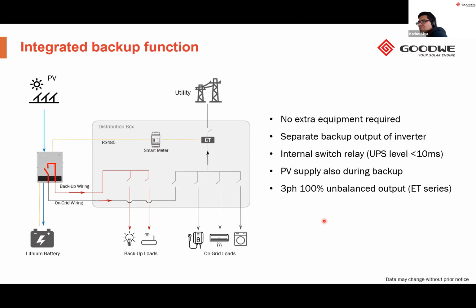There is a special feature from the PV Master app which you can activate. And for those people, or my friends out in the Czech Republic, who really need a true zero output, the unbalanced output is the way to go to ensure that you have no electrons flowing out from any of the phases back into the grid.